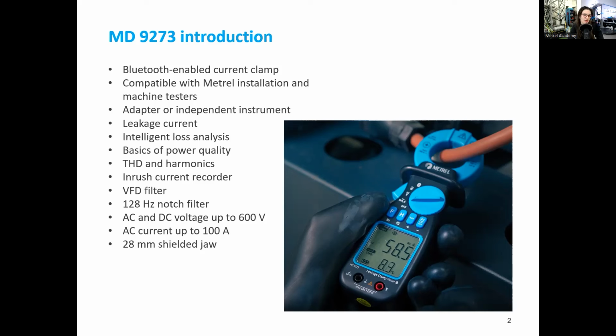Finally, we have the basic multimeter abilities. We can measure voltage in TRMS, AC, or in DC. We have the secondary measurement of frequency. We have the AC current up to 100 amps. And we have the basic recorders of minimum value, maximum value. We can hold the value. There is the peak function for catching fast signals. And finally, we can measure the crest factor, which can tell you more about the type of signal and its difference from the ideal sine.